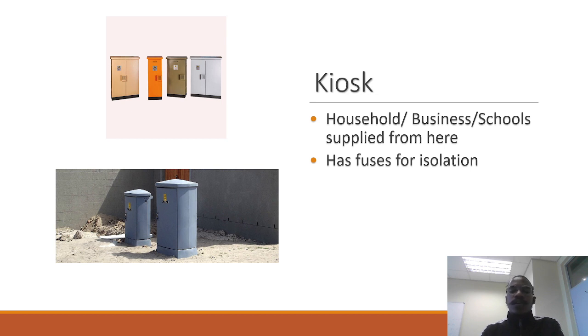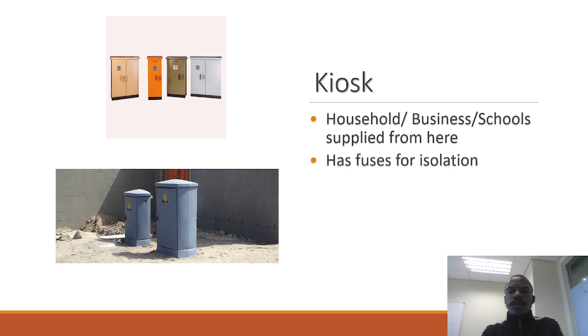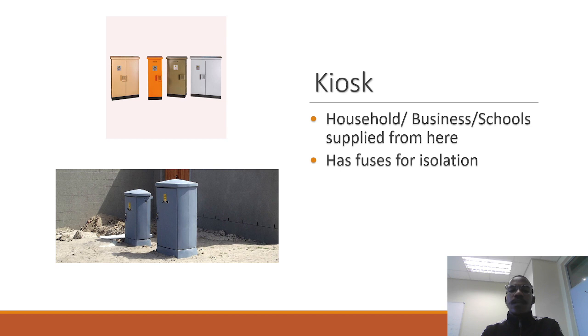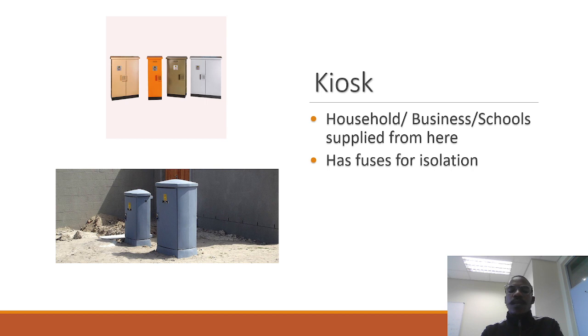The kiosk has got various isolators. In fact, in electricity there should always be an isolation point. So you have an isolation point in the miniature sub and you have an isolation point in the kiosk. The kiosk will have its own isolation point based on how many houses it can take. Some kiosks may be 12-way, some kiosks may be 18-way. It just depends on the council specification as to how many houses you can put on that kiosk, but maximum houses you can put on one kiosk is either 12 or 18.